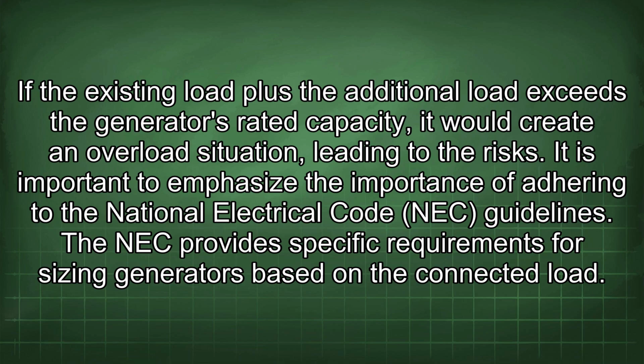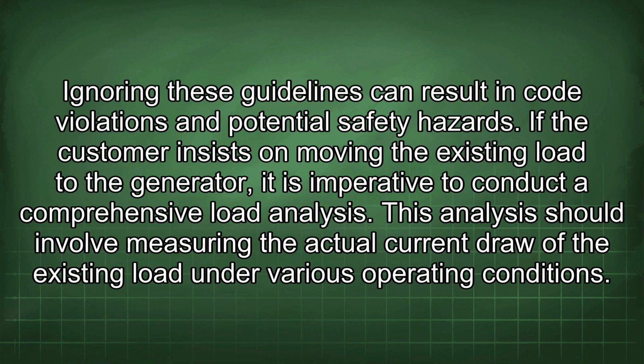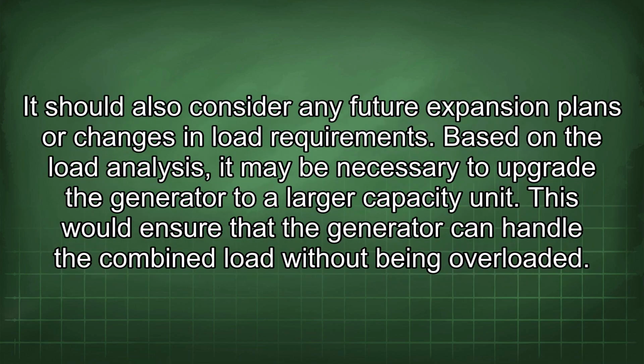The NEC provides specific requirements for sizing generators based on the connected load. Ignoring these guidelines can result in code violations and potential safety hazards. If the customer insists on moving the existing load to the generator, it is imperative to conduct a comprehensive load analysis. This analysis should involve measuring the actual current draw of the existing load under various operating conditions. It should also consider any future expansion plans or changes in load requirements.